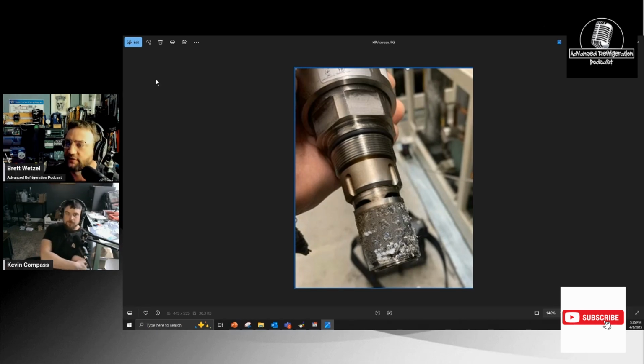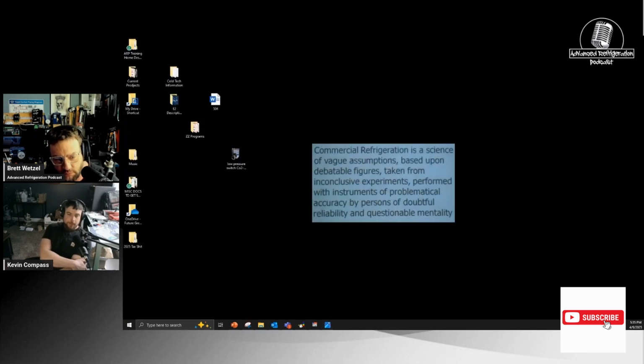So just have it. Yeah, and I would say at least one time after startup or within a year of runtime, it should be cleaned out. Generally, when you're looking at these valves, if you see them more than 60, 70% open, and your head pressure's not super low, driven down, that valve's plugging up.